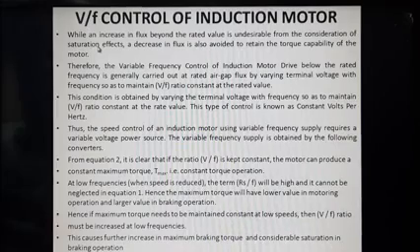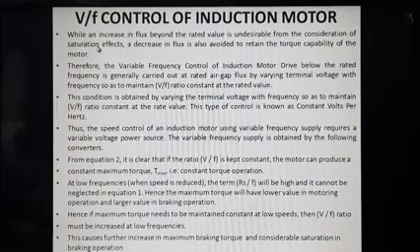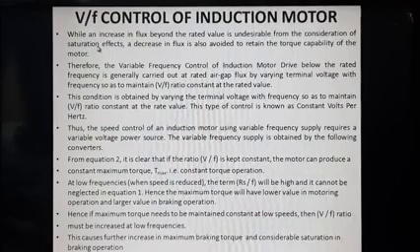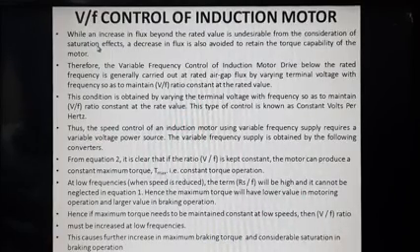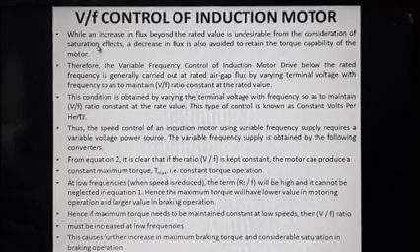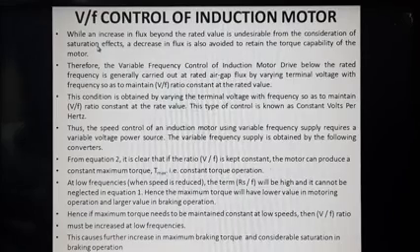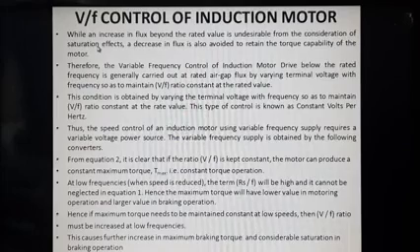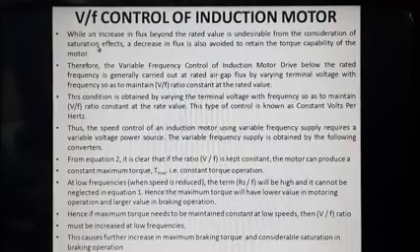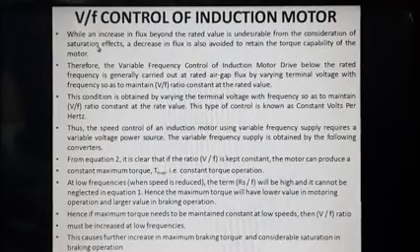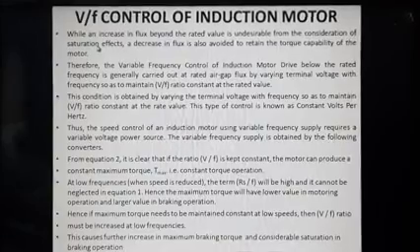So if we are trying to reduce the speed by reducing the value of frequency, definitely the value of flux will increase and it will go beyond the knee point. That means the operating point will be shifting from the knee point to the saturation point, which creates some undesirable effects. In the same way, if you are trying to increase the speed by increasing the value of frequency, then the maximum torque capability of the induction motor also gets reduced.